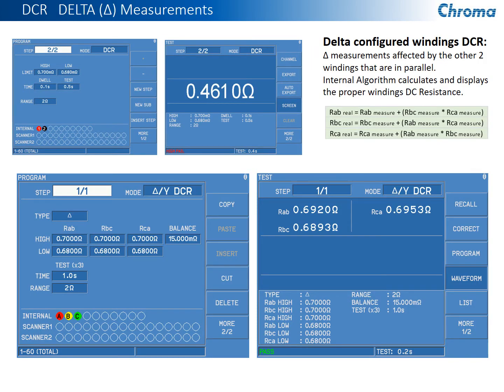When we look at it on the unit itself, on top here I've got a standard DC measurement without doing any type of calculation regarding a delta or a Y type measurement. Here you can see the winding I measured, which is the same winding as RAB on the 3 phases, measured 461 milliohms or 0.461 ohms. And you'll notice here that when I measured it using our delta connection, our delta calculation, it came out to be 692 milliohms, which is the proper resistance of that winding.